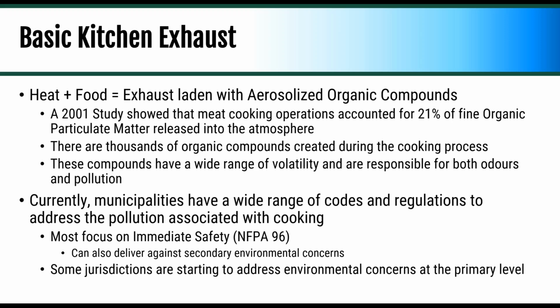It's not one of those things where, obviously, when you look at NFPA 96, that's really looking at immediate safety, i.e., let's not burn down the building. Let's make sure everybody has a good dining experience. If there is a fire in the kitchen, it should be contained in the kitchen and extinguished in the kitchen, and the kitchen should be able to reopen relatively quickly. Everybody should be safe.